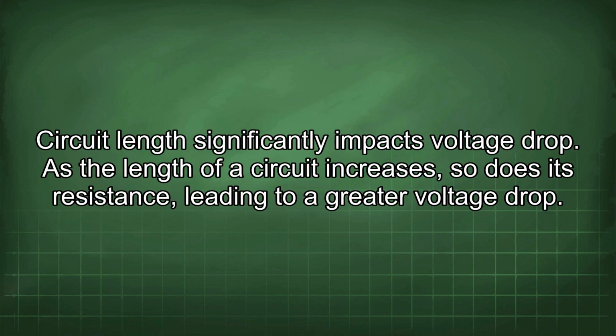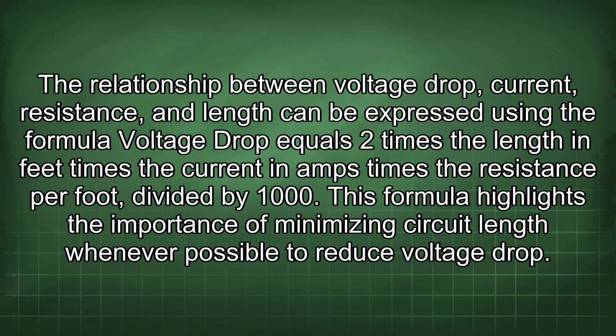Circuit length significantly impacts voltage drop. As the length of a circuit increases, so does its resistance, leading to a greater voltage drop. The relationship between voltage drop, current, resistance, and length can be expressed using the formula: voltage drop equals 2 times the length in feet times the current in amps times the resistance per foot, divided by 1000. This formula highlights the importance of minimizing circuit length whenever possible to reduce voltage drop.